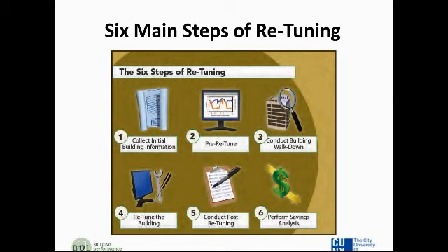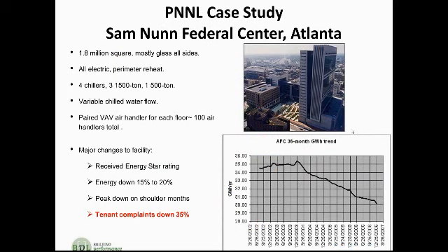Gathering data afterwards is always a good idea, because that enables you to perform a savings analysis. Obviously, that's not required, but it is preferred, because if you do justify the amount of savings you've realized, sometimes the savings are 10%, 20% overall building energy savings from things that can easily be overlooked. Once you identify those things, those are fantastic justification for either more budget for other related measures, or maybe even other projects you might want to take on. So that's always good for reporting back to the managers and those that hold the purse strings.